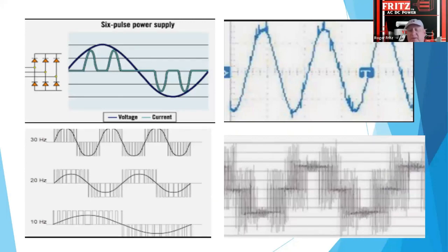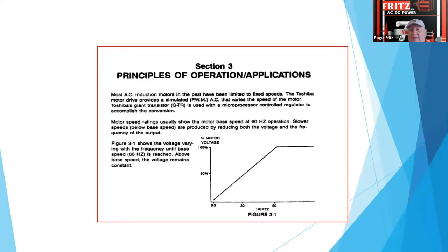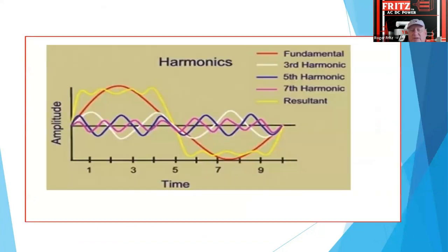So when you have this PWM going out, depending on how long the lead lengths are out to the motor, you create a different amount of inductance and resistance to the motor. So literally, you're a voltage supply. You'll see these extra spikes, and that's what destroys, especially, older motors. It seemed like from about the '85, '90 on, they all put in spike resistant wire, but some of the earlier ones didn't have it. So you had motor failures.